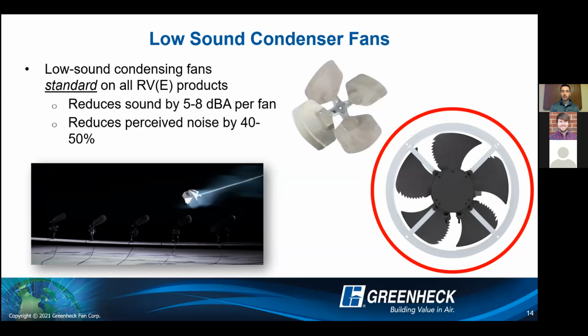So that low sound condensing fan actually reduces sound by about 5 to 8 decibels per fan, and it's actually a perceived noise reduction of about 40 to 50%. So when we're at that 60, 70 ton range, we have 8 condenser fans, 8 condenser fans being that low sound condenser fan design versus that typical paddle blade type condenser fan, that really reduces that sound. So again, a nice feature that we always have on RV/RVE, a nice thing to hold in your specifications to make sure that you're getting equal condenser fans from others as well.